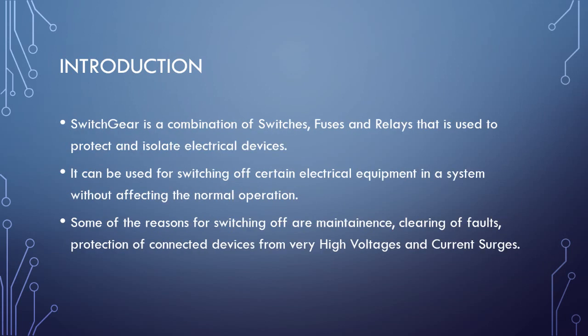A switchgear is a combination of switches, fuses and relays which is used to protect and isolate connected electrical devices. It can be used to turn on and off connected electrical devices in a system without affecting other connected devices which may be separate from the switchgear. There could be a number of reasons for breaking the circuit and de-energizing the equipment: inspection, maintenance, clearing of faults, or even automatic shutdown due to high currents.